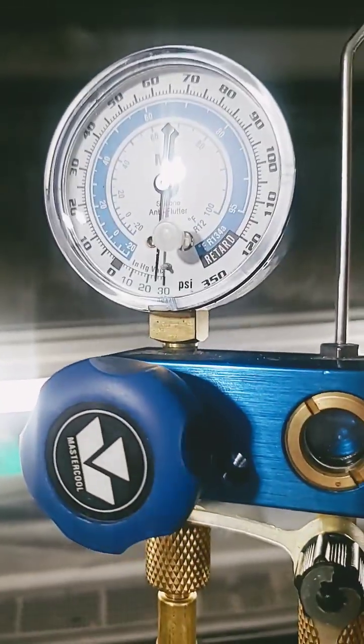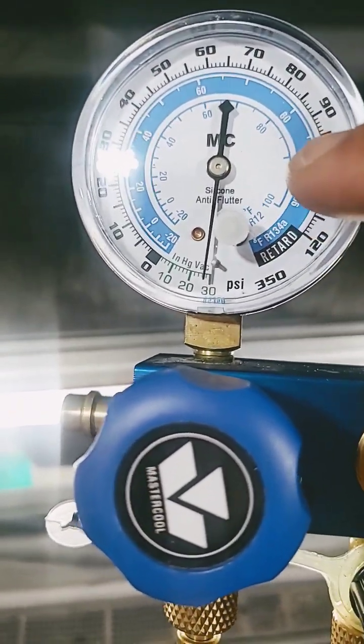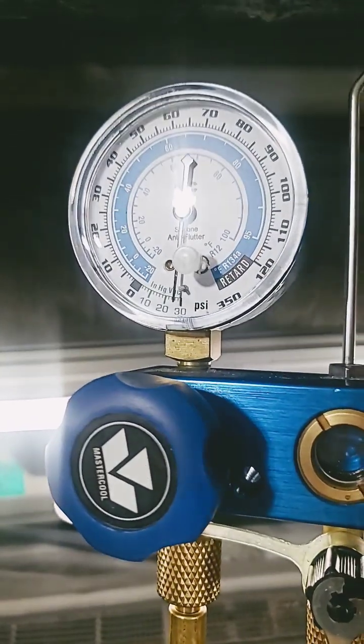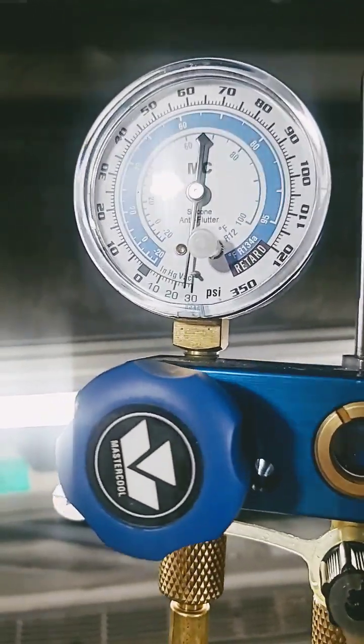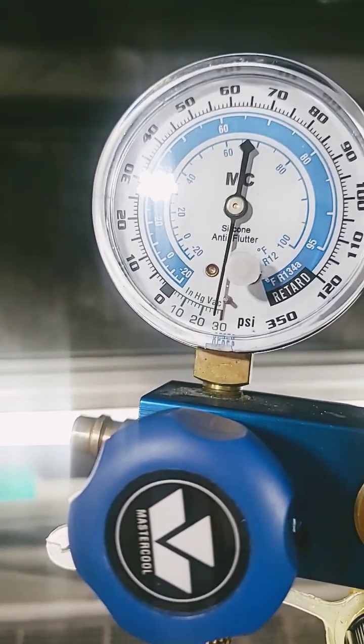So don't get that confused. So your pump is still good, it's just you can't pull a vacuum because you have a leak. So that's the whole point of using a vacuum pump so you can verify whether if your system has a leak or not.